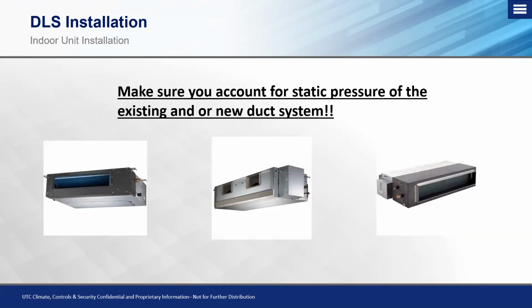And again, don't assume that the units are set up automatically to recognize airflow such as static pressure and the amount of CFM. We still need to take our load calcs for the individual spaces. We still need to look at the product data of the units to make sure that the unit that we're selecting is going to give us the appropriate amount of static pressure to output proper airflow into the spaces that we're trying to serve. For example, the 9 and 12,000 BTU units are only going to give you about 0.2 inches of static max on those. So those are going to be best for one-to-one applications with no takeoffs.